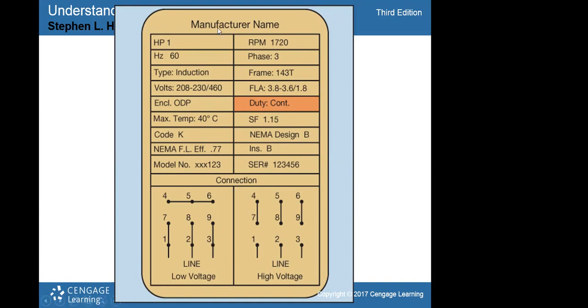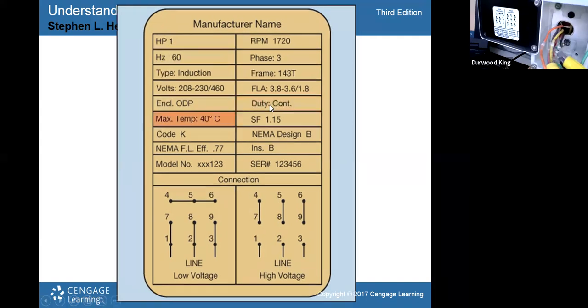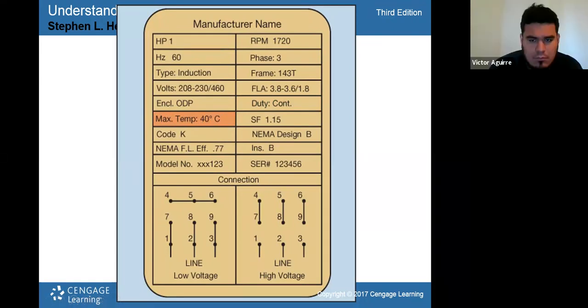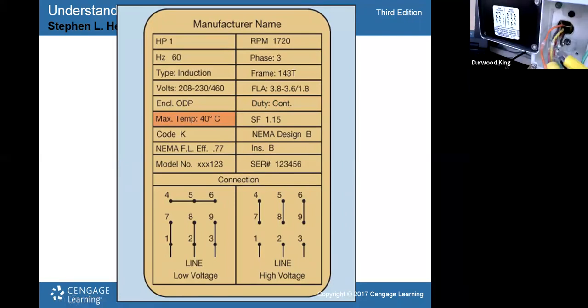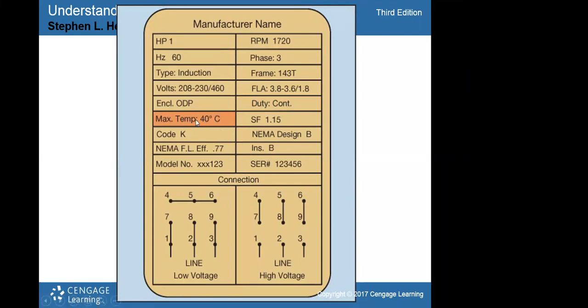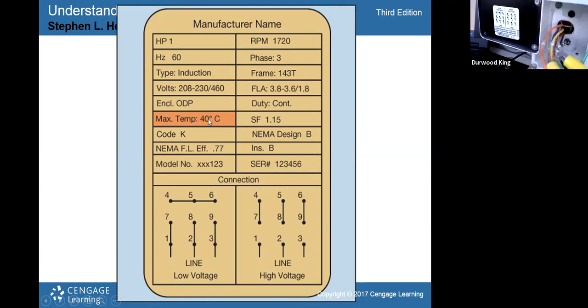Most motors are going to be continuous duty. And then maximum temperature. What that's referring to is actually temperature rise. That 40 degrees C is how much rise in temperature the motor could exhibit above ambient temperature. Whatever room you're in, you could expect that motor to run at 40 degrees C higher than ambient. So it's giving you a rough ballpark on how hot the motor could run above ambient.